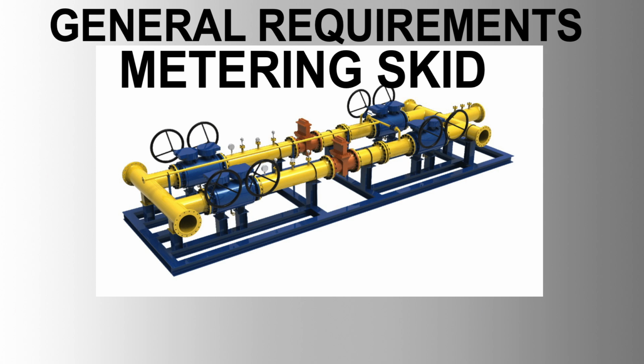Skid arrangements. Metering systems should be mounted on skids for easy transportation and installation. Skids should include inlet and outlet headers with flanged connections to the parent line. Closed drain and vent headers should be included, with connections defined by the contractor. Isolation valves upstream of the meters should be manually operated, while downstream valves should be motor-operated double block and bleed with relieving facilities. Skids should be provided with lifting lugs and earthing lugs for safety and ease of handling.